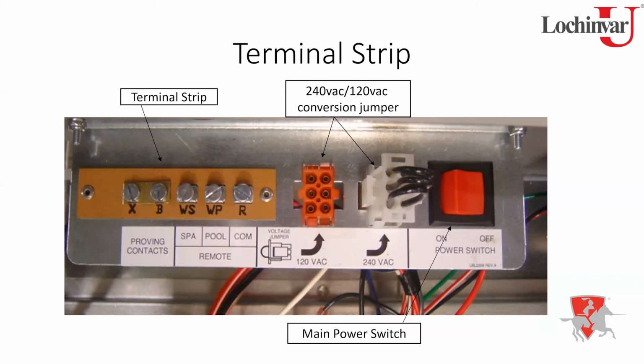Now the heater itself comes equipped for either 240 or 120. As it leaves the factory, the little jumper here should be in the 240 volt position. And that's kind of important, right? Why do we want to do that? Yeah, so here's what I've seen in the past. This is something else I want everybody to pay attention to. It may help you out on a brand new startup. You see that 240 jumper plug comes in the 240 position.